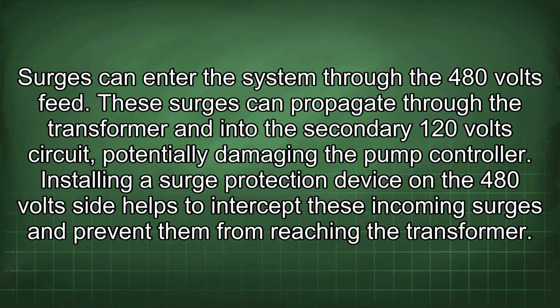Surges can enter the system through the 480 volts feed. These surges can propagate through the transformer and into the secondary 120 volt circuit, potentially damaging the pump controller. Installing a surge protection device on the 480 volt side helps to intercept these incoming surges and prevent them from reaching the transformer.